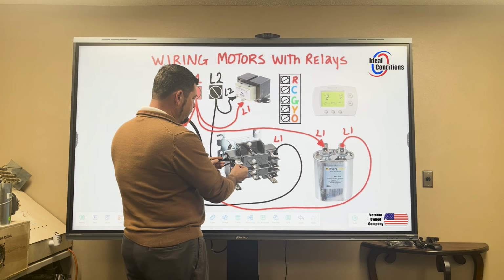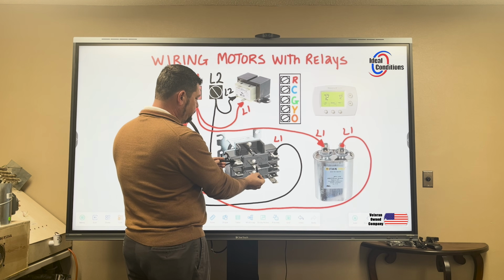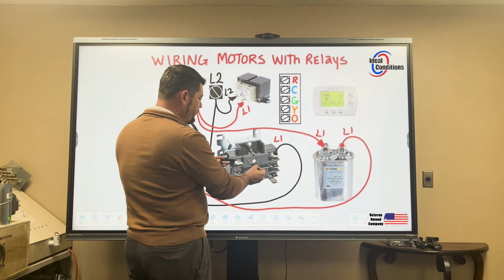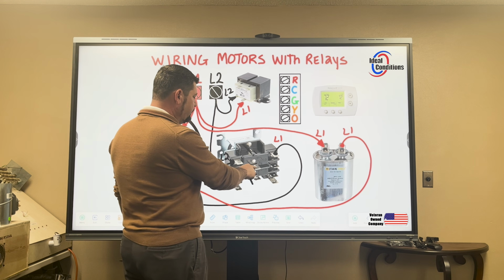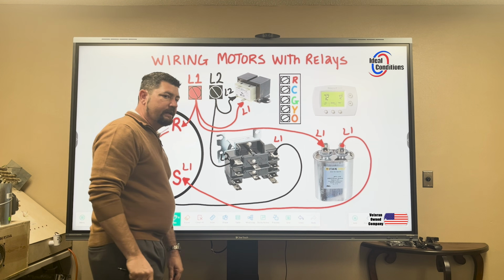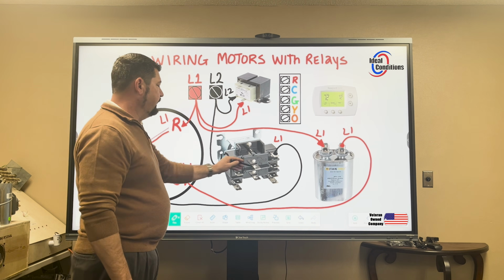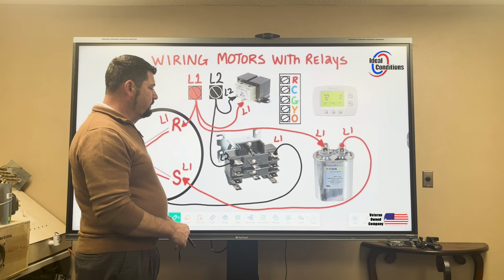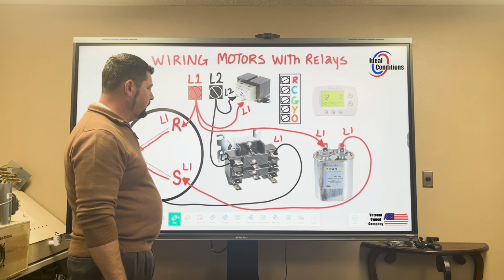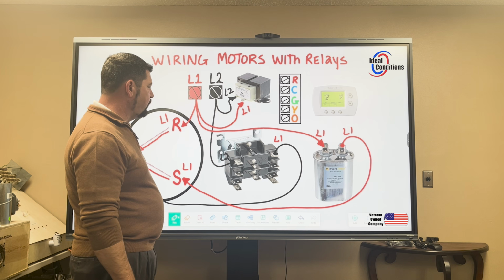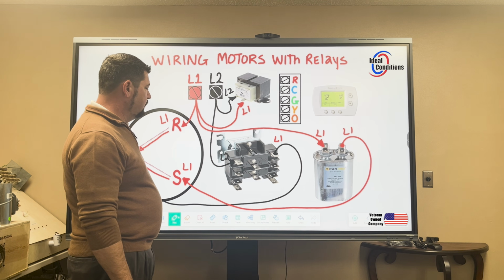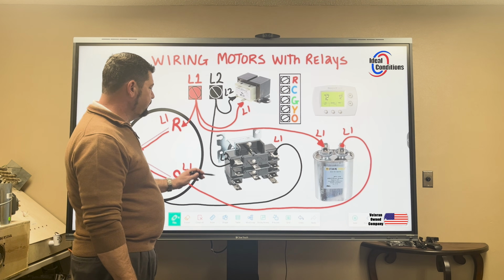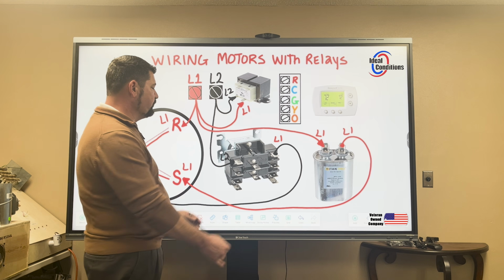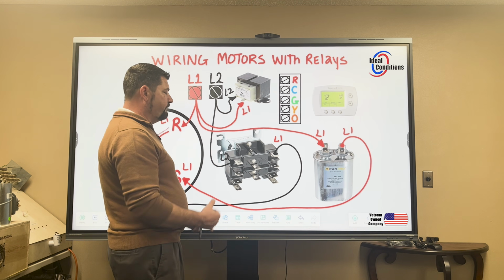Now, if I put my meter from here to here on terminal 2, even though I don't have anything wired up to it, I'm going to read 0 volts. But if I were to touch terminal 2, I will get electrocuted from the second leg. And so we demonstrated that earlier when we were at the light bulb, where power was present. So we always have to respect electricity. Just because you read 0 doesn't mean there's not voltage.